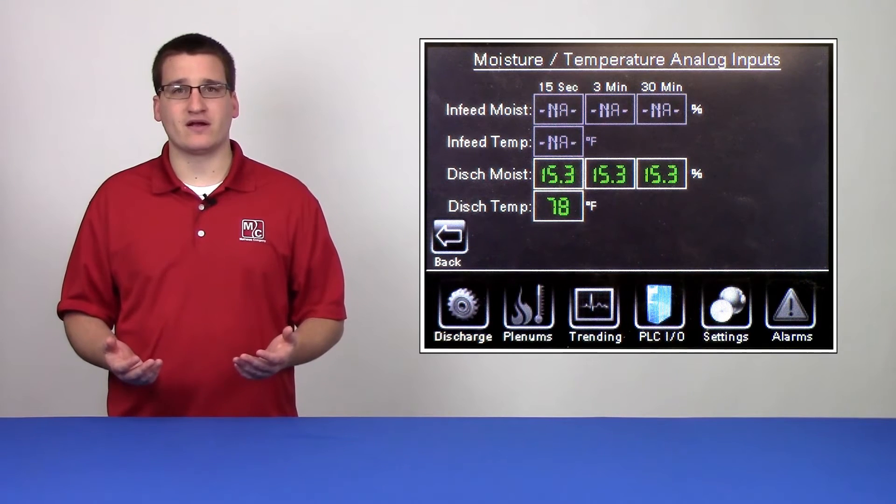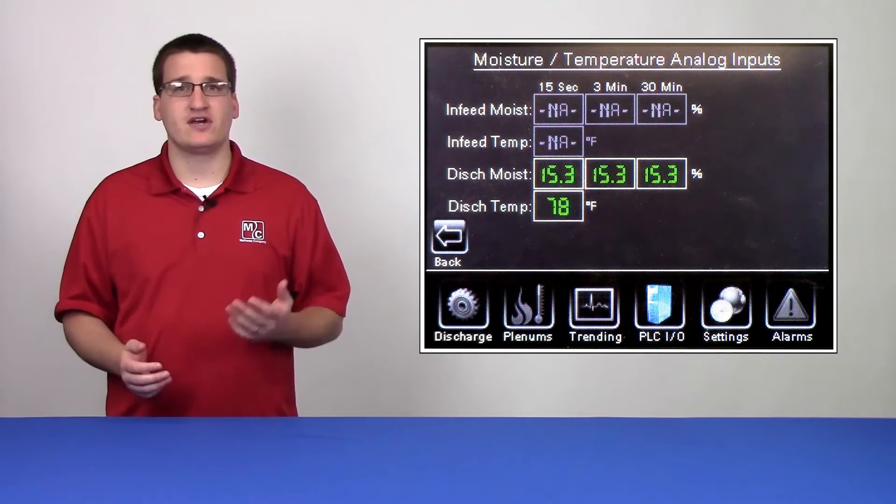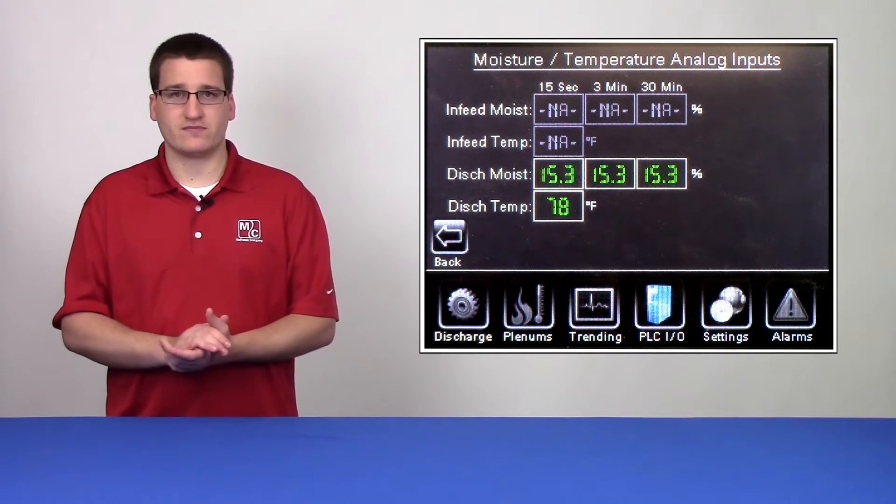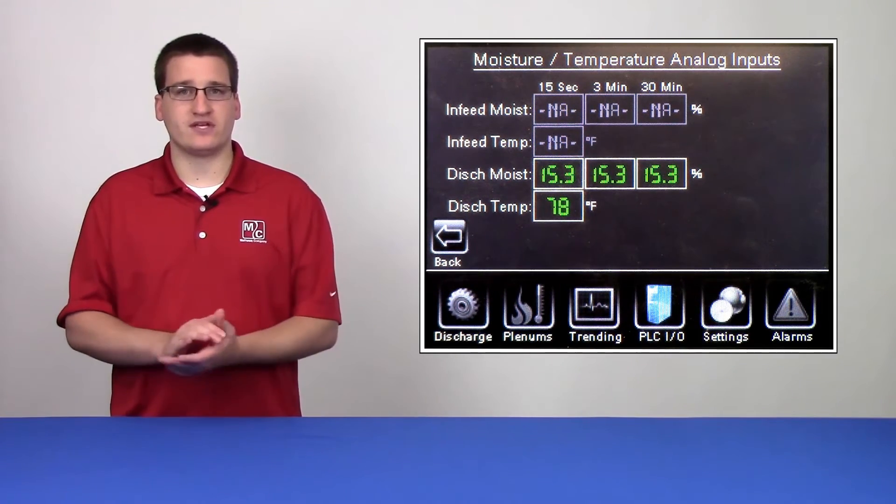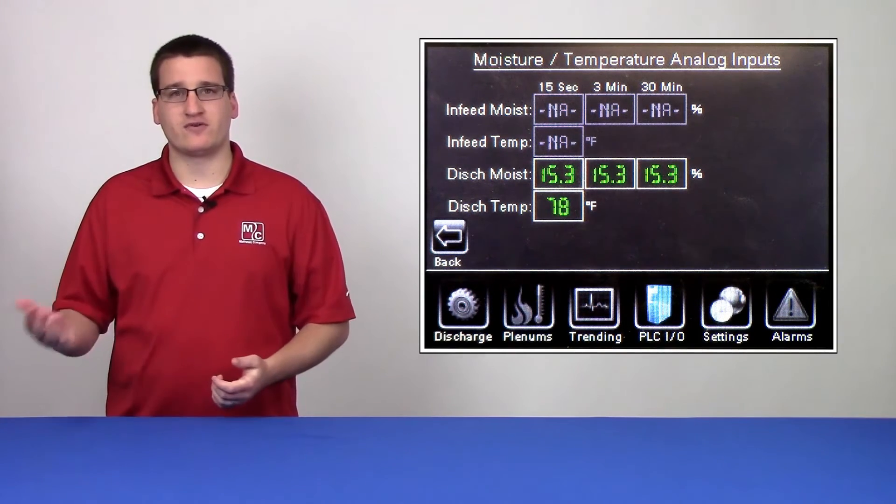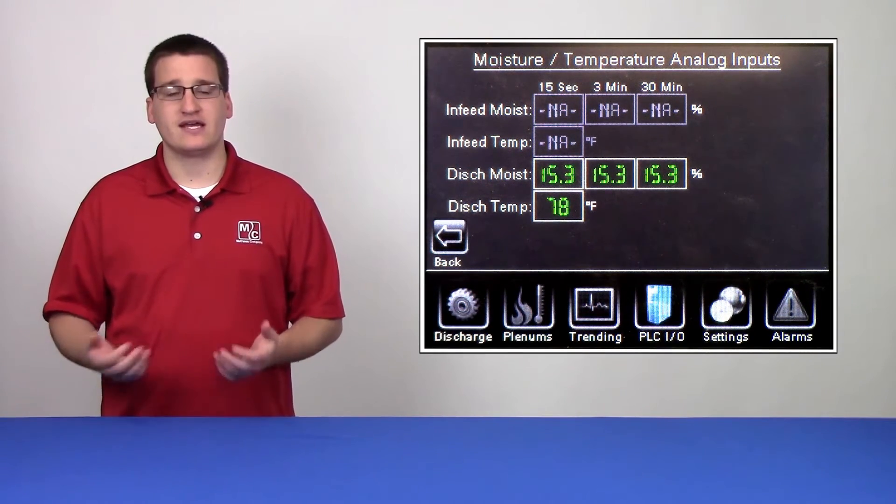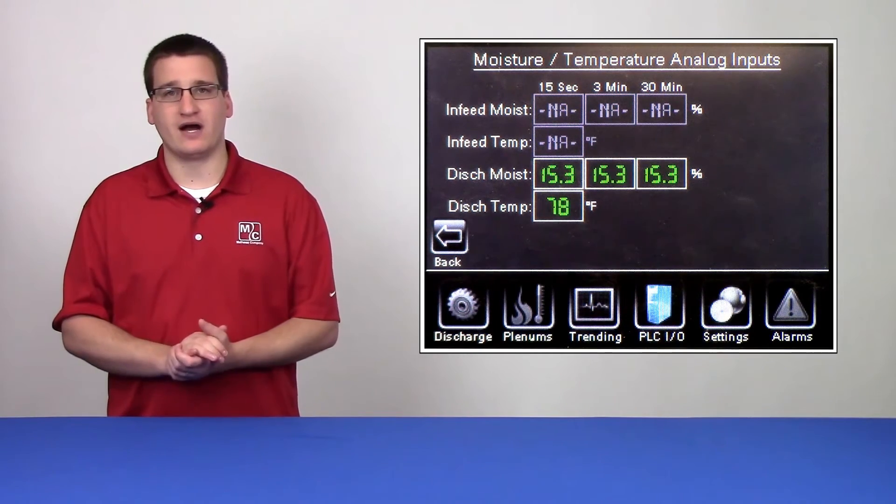Next, we'll compare the dryer's result on the 15 second average versus the tester's result. If we say that the tester in this example read 14.3 on average and our dryer read 15.3, that tells us that the dryer is reading 1.0 high.